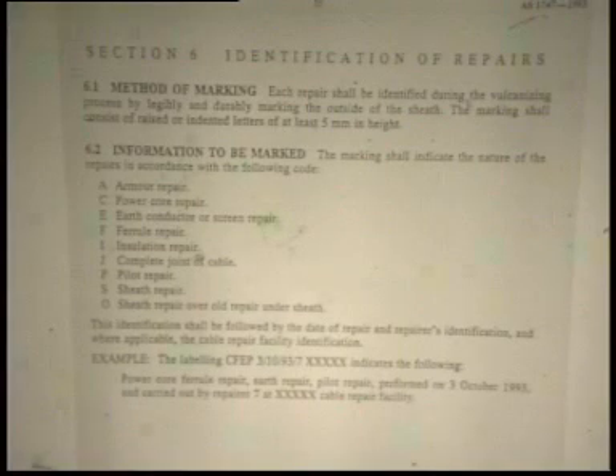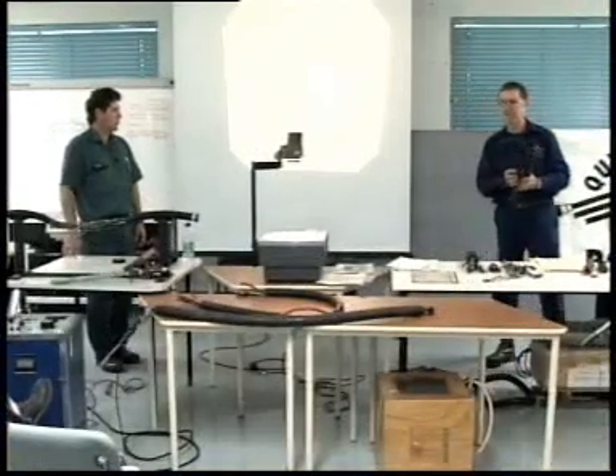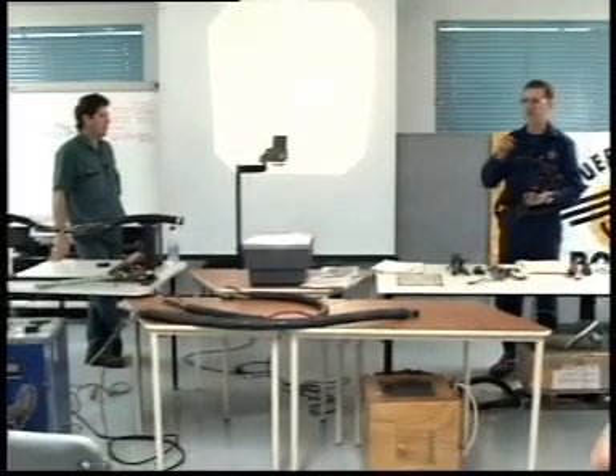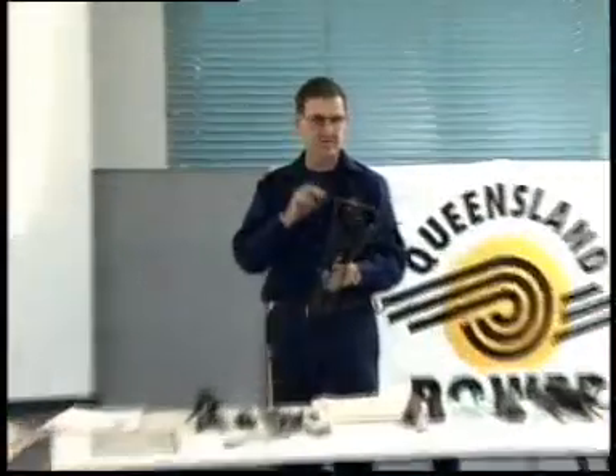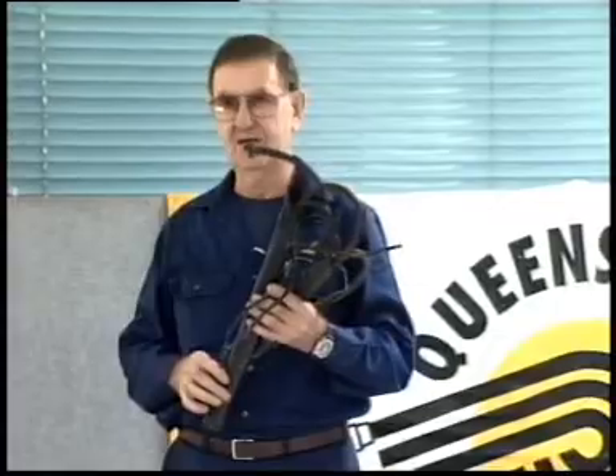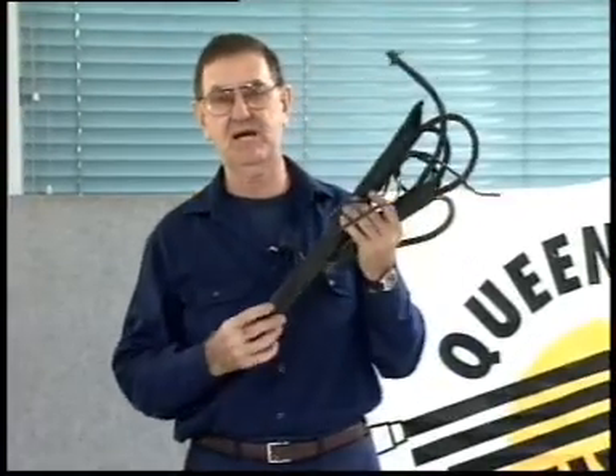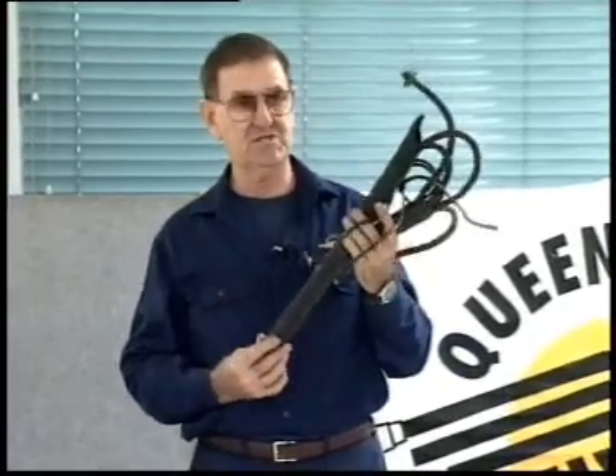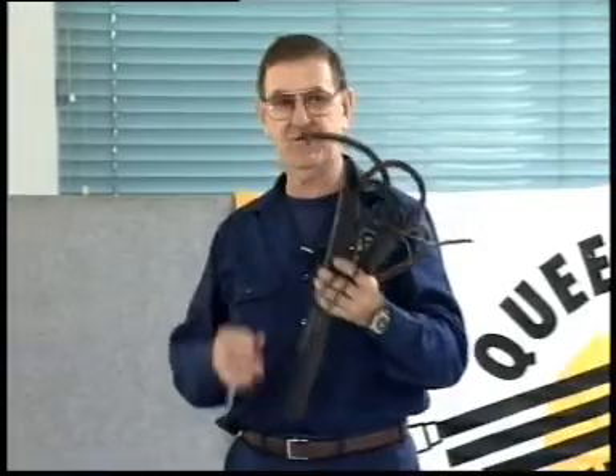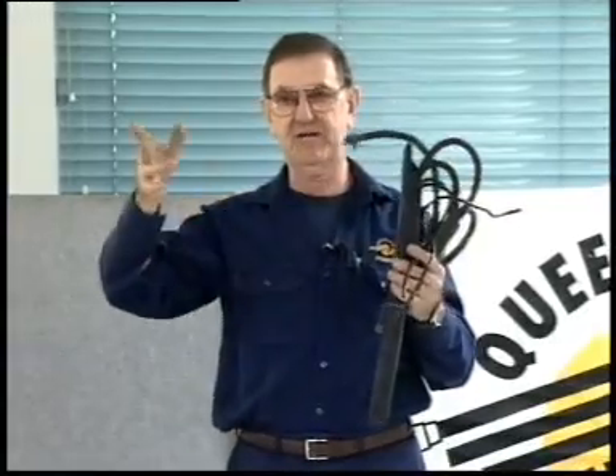So anywhere you see on these cables where there's been a repair, that's the repair from the Australian standard that you're looking at on the board up there. That tells us exactly what the repair is underneath the outer sheath. At one of the classes where we were at, a particular person told us that the reason the pilot wire or the earth continuity wire was through the centre here was so that if you did stretch the cable and it busted, it'd break that small wire first and drop the power off before these main conductors parted and created a flash.